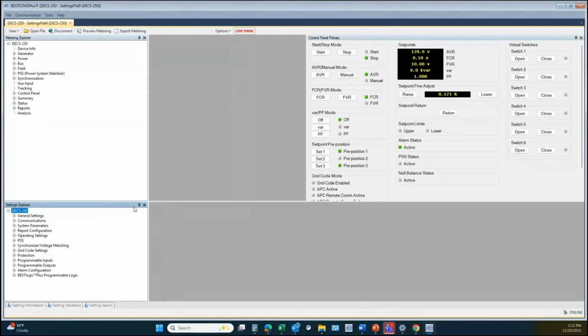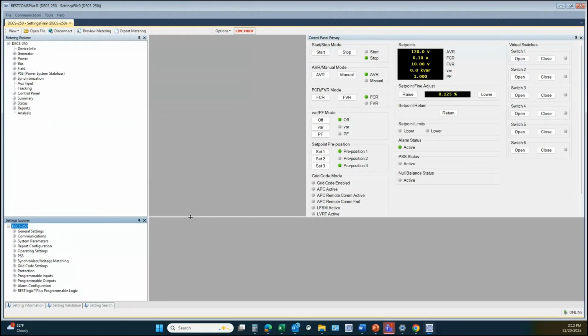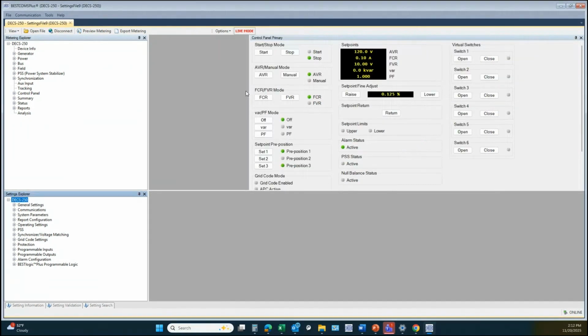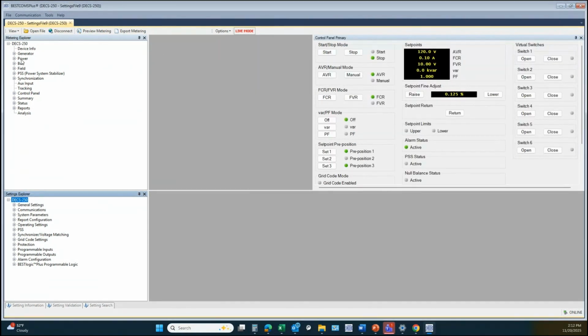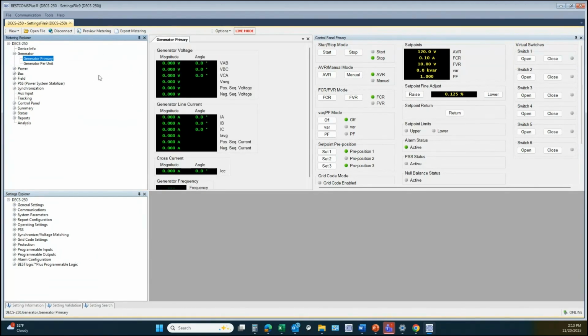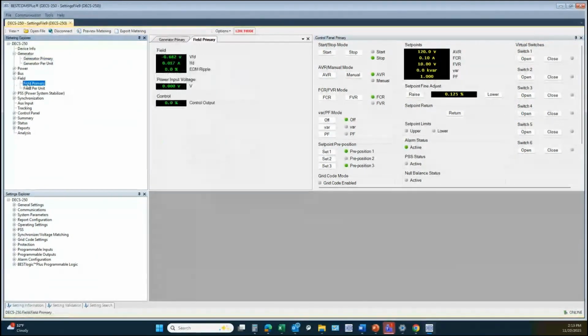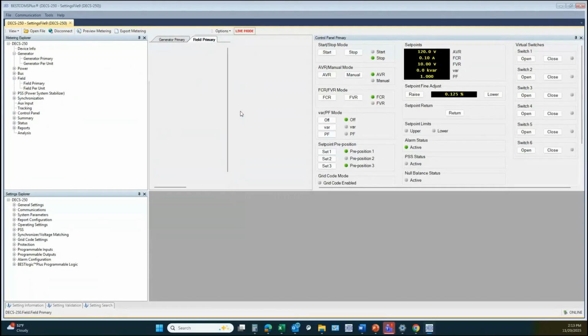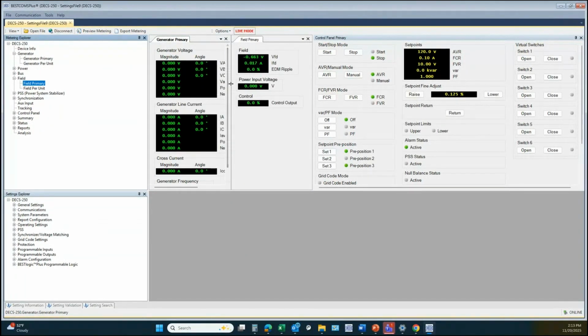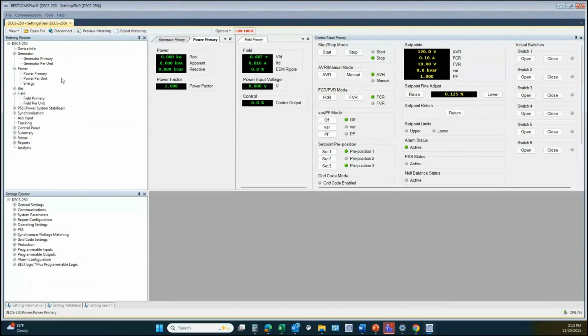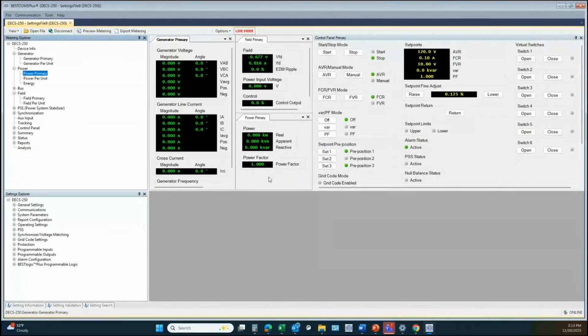And the division line between those two can be dragged around so that you can have one section of the software take up more of your open space than the other. And the same applies to these metering screens. You can drag those around as well. So if I open a metering screen and go to generator primary, for example, but I also want to see the field primary at the same time, I can drag those around and allow them to populate different areas of the screen. If I want to add power, I can add power. So being able to manipulate the metering screens can be very useful whenever trying to view multiple items simultaneously while communicating with your unit.